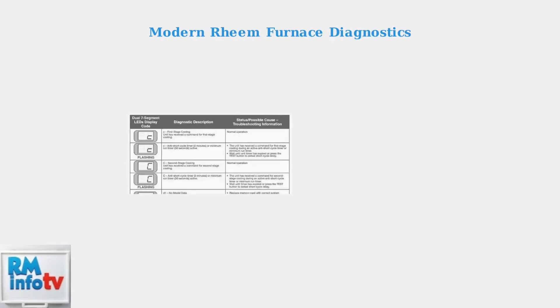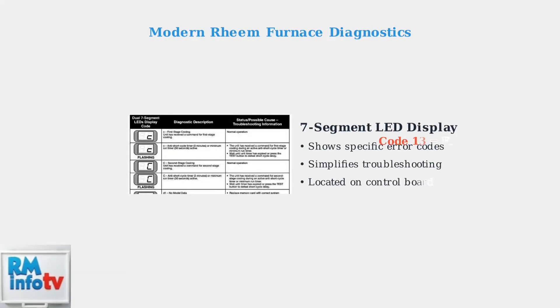Additional causes include inducer motor problems that affect airflow and venting. Modern Rheem furnaces use a seven-segment LED display to show error codes, making troubleshooting much simpler than older models. This display is located on the furnace control board and provides specific diagnostic information to help identify problems quickly.